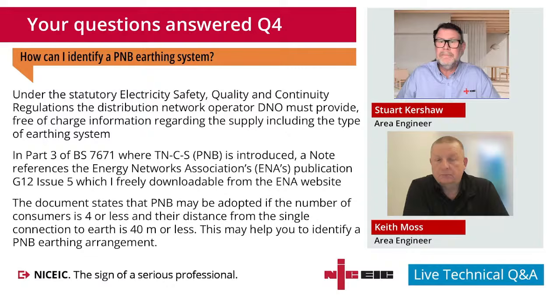yeah, because it'll have that single point of reference to earth, and the guidance to the DNOs is it should be as close to the consumer's terminals as possible, and certainly 40 metres or less. So that's one thing that might tell. But as Stuart said, if in doubt, it's a query to the DNO, and that's information that they must provide free of charge.